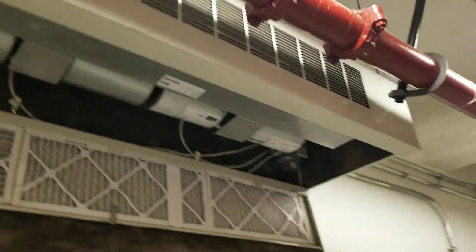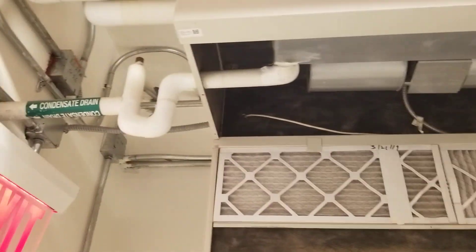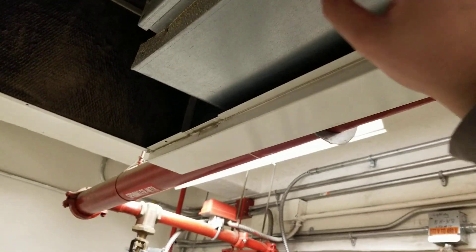It's just a little hoist room here for the elevators. We have a condensate drain, blowers, and motors. Here we have four blowers — one dual blower here, one dual here. There's a little condensate pan up here that'll pop down so you can check it. You might think you have to take the blowers out to get to it, but this is it right here. You've also got a little speed controller up there in the corner for your fan speeds.